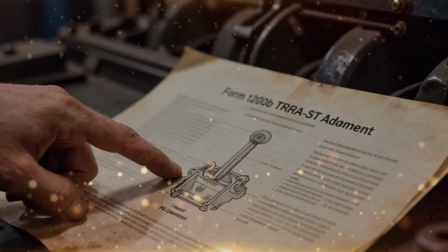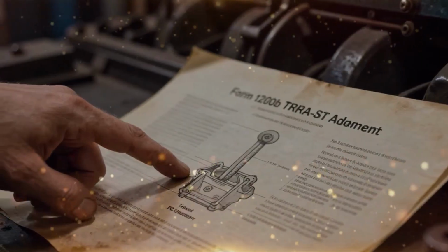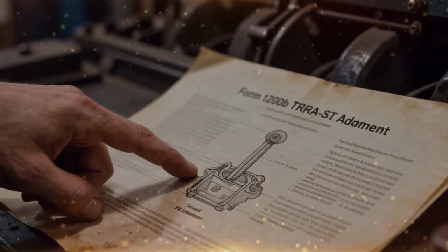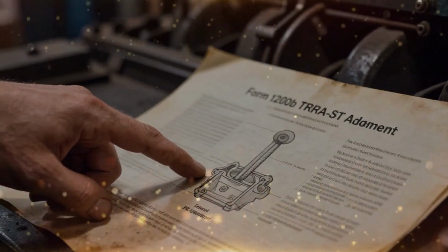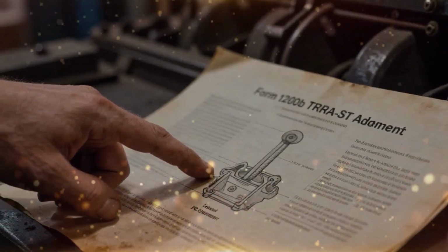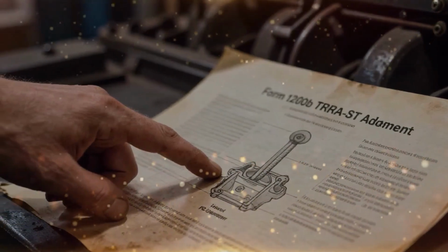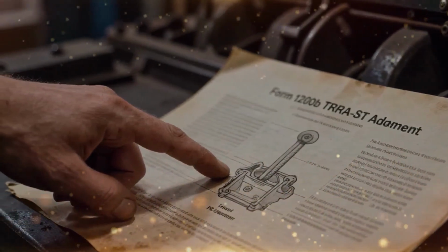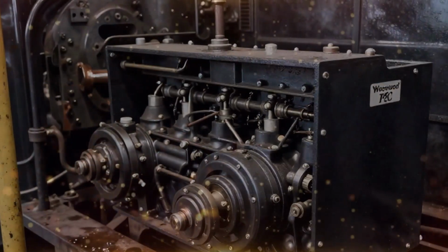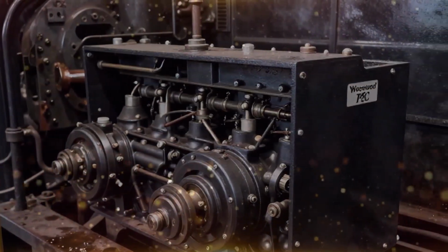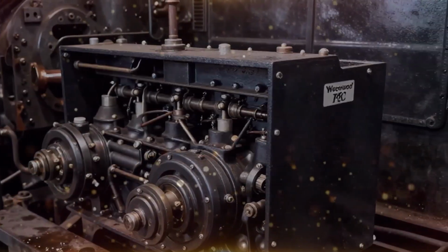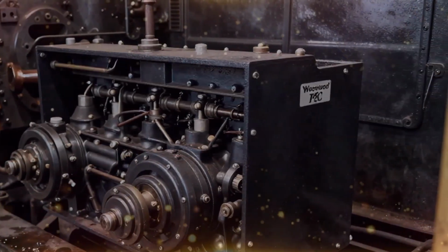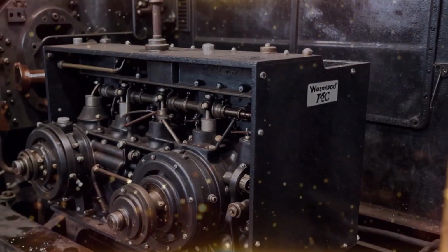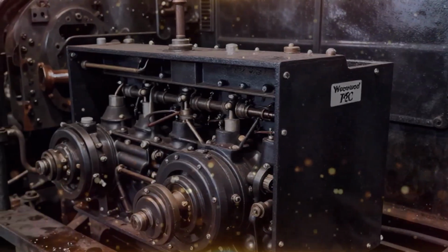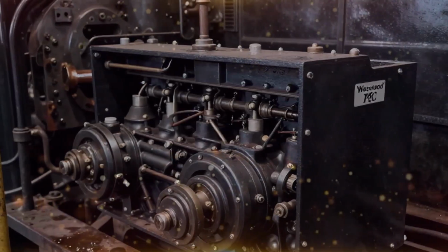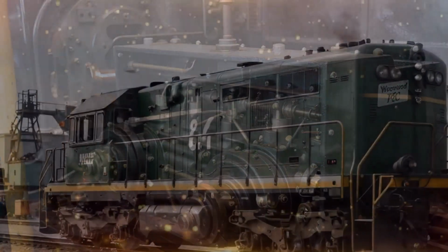This addendum didn't just list pressure settings, it detailed a specific mechanical deviation from the standard assembly. It described the blueprint secret that had eluded 8 professional repair crews. The document specified a shimming requirement for the governor pilot valve radically different from the standard zero lash setting. The text was explicit. It called for a negative lash, or a preload on the pilot valve spring, achieved by inserting a specific thickness of shim stock between the floating lever and the valve plunger.